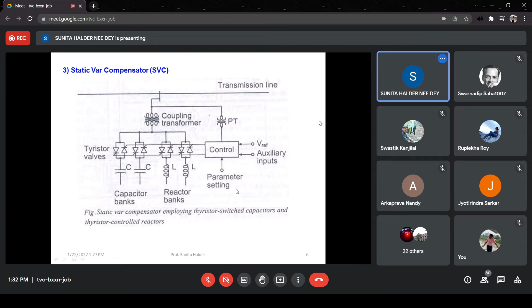There must be some V reference at which voltage we want to set the bus voltage. It will be compared with the available bus voltage, and accordingly the capacitor and inductor will be switched on. Here it is written static Var compensator employing thyristor switched capacitor and thyristor controlled reactor. That means on the capacitor side, thyristors are used only for switching, and on the inductor they are used for current control. Static Var compensators are directly not in your syllabus, but they should be known in the undergraduate class. So I am discussing this one.